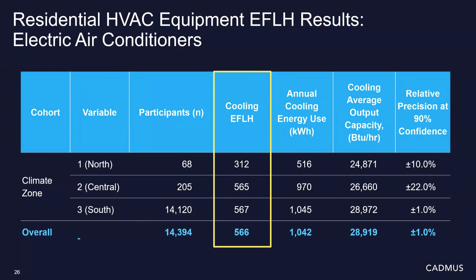This slide shows the air conditioning equipment participants' cooling EFLH results, annual cooling energy use, and the average output capacity for air conditioning participants. The EFLH varied from about 312 hours in zone 1 to 567 in zone 3. Note that zone 2 and 3 were very similar. While most of the participant data was from zone 3, it did achieve the highest precision, or lowest precision number, at 1% at 90% confidence. The precision did vary pretty significantly from 1% to almost 22% for zone 2.